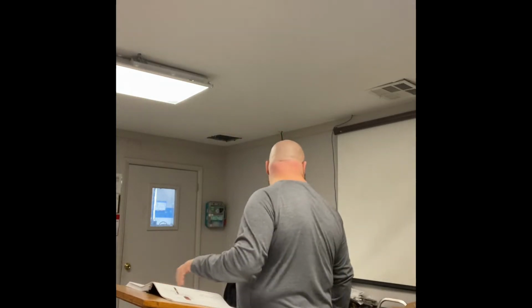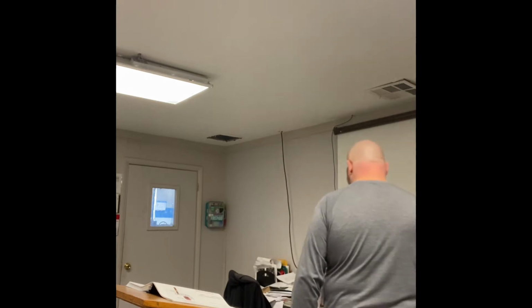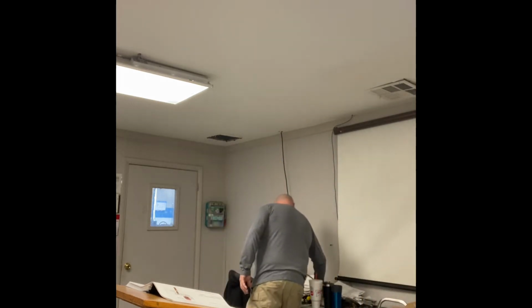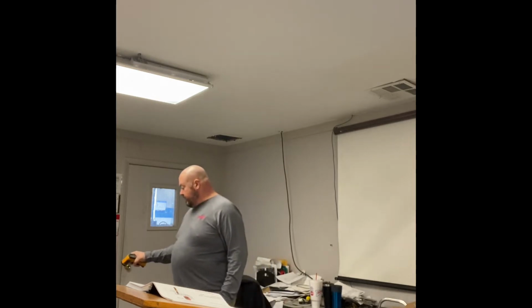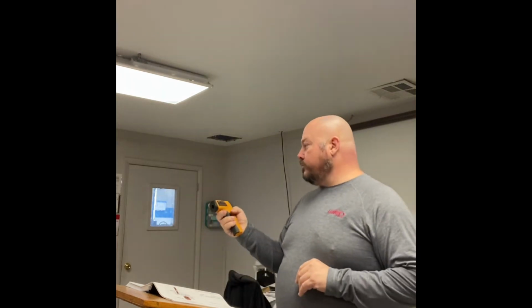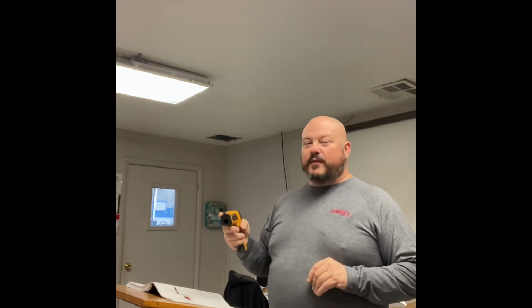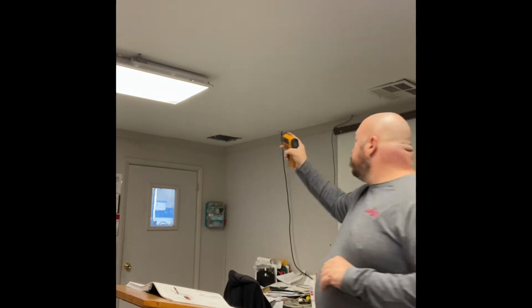Okay? I'm gonna look through my tool bag. I'm gonna find my temperature gauge. Whether you're using one of those toys, one of the little laser guns, and you're going through and shooting the ducts and seeing what the fake numbers are, all you're really doing, this is great for finding a temperature difference. It's not accurate, but it's accurate enough to go, there's 15 degrees difference between here to there. Perfect. Okay? It can read in its range where it's calibrated at.